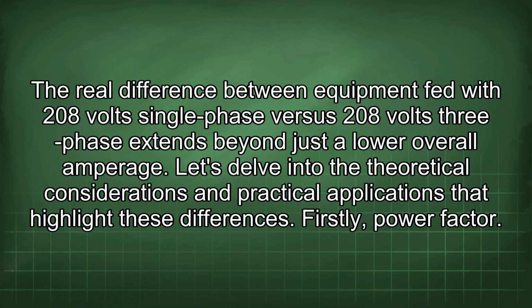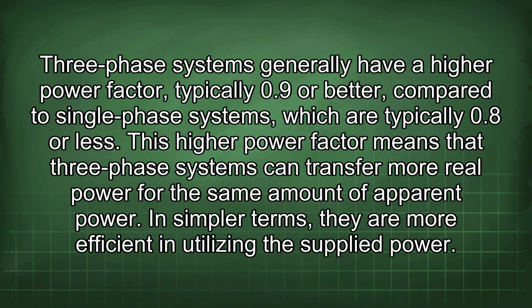The real difference between equipment fed with 208 volts single-phase versus 208 volts three-phase extends beyond just a lower overall amperage. Let's delve into the theoretical considerations and practical applications that highlight these differences. Firstly, power factor. Three-phase systems generally have a higher power factor, typically 0.9 or better, compared to single-phase systems, which are typically 0.8 or less.